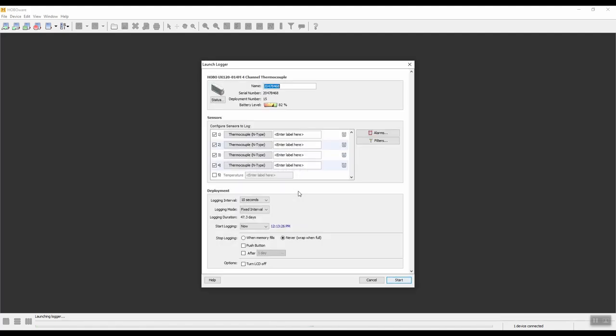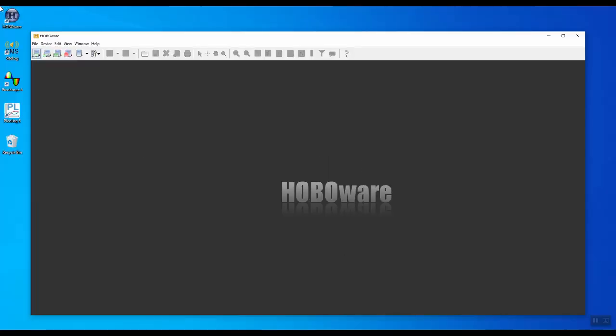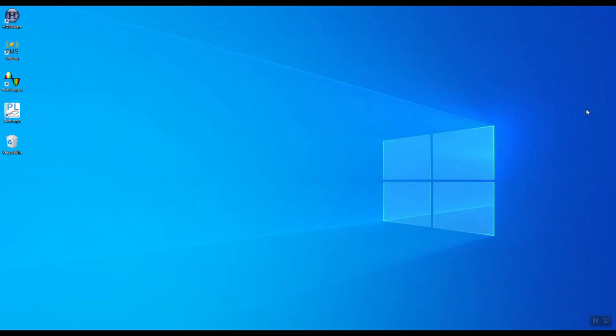Now let's remember the configuration that we had and we can just click on start. If however for some reason you do not get this and you want to reconfigure it, just simply follow the instructions that we had earlier in the video to configure the channels, the sampling interval, when to start logging, and what to do when the memory fills up, either stop logging or wrap when full. So we're happy with these current settings, so we'll click on start. Now this is going to write the configuration to the logger just as it did in the beginning of the video. So now the logger is ready to use. We can exit the software and disconnect the logger. You'll see that the Hobo logger screen appears from being blank to showing us some values.